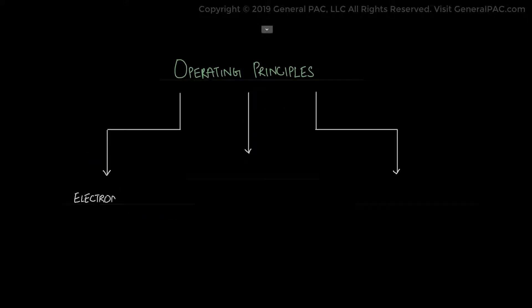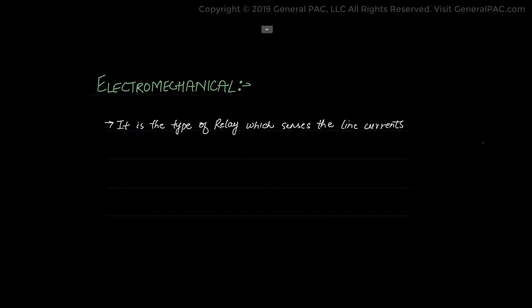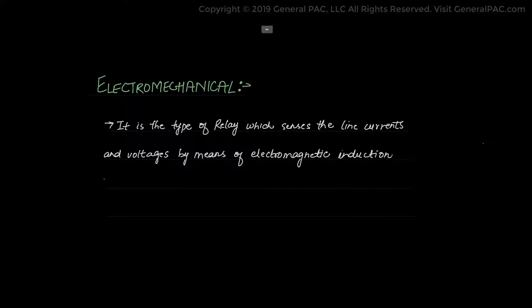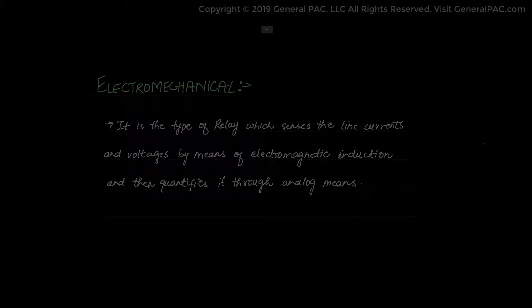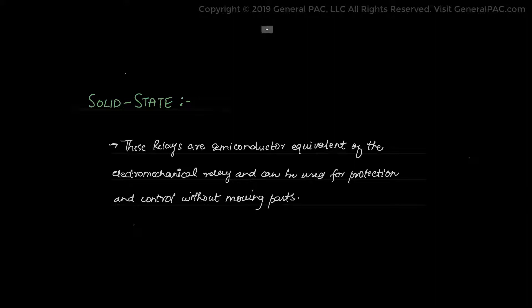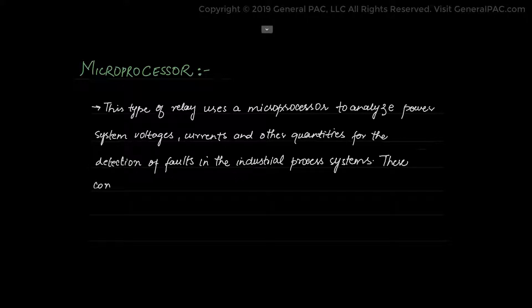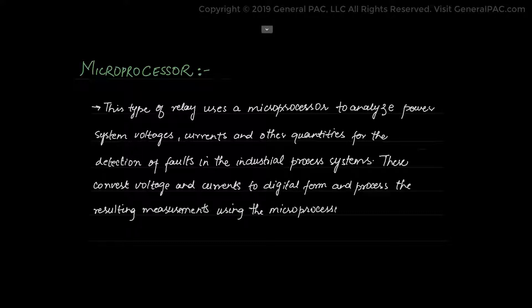There are three main operating principles for protective relays: electromechanical, solid-state, and microprocessor. Electromechanical is a type of relay which senses the line current and voltage by means of electromagnetic induction and then quantifies it through analog means. Solid-state relays are semiconductor equivalents of electromechanical relays and can be used for protection and control without moving parts. Microprocessor relays use microprocessors to analyze power system voltage and current and other quantities for the detection of faults in the industrial process system. They convert voltage and current quantities to digital form and then process the resulting measurements using the microprocessor.